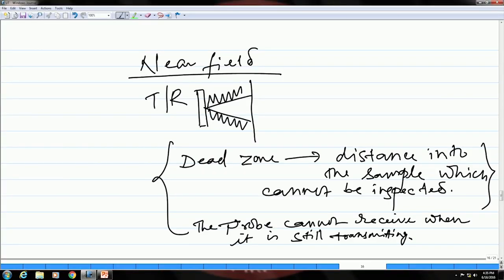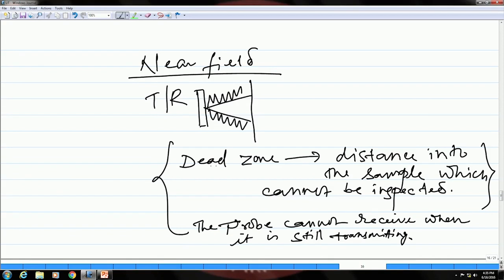If the vibrations are still there and by the time an echo comes back to the transducer, it will not be able to receive that echo while it is still vibrating. So that is the effect of the near field, which gives rise to this dead zone.